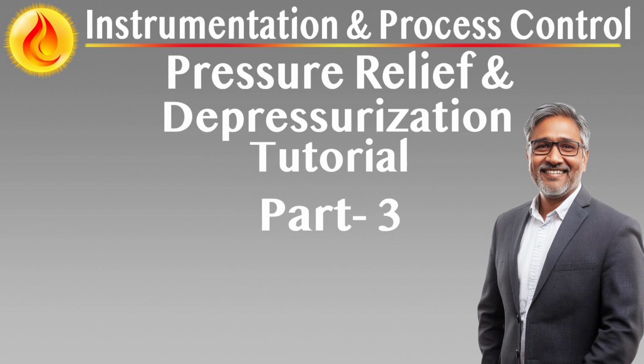Emergency depressurization is typically initiated by operators or automatically in unmanned facilities. It must be possible to activate the system remotely, most commonly from the control room or a designated safe area. These systems are not used for routine shutdown or maintenance venting. They are designed solely for rapid pressure reduction during defined emergency events and must be treated as part of the facility's critical safety layer.